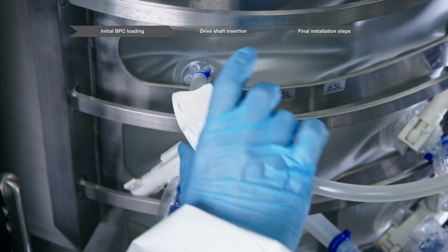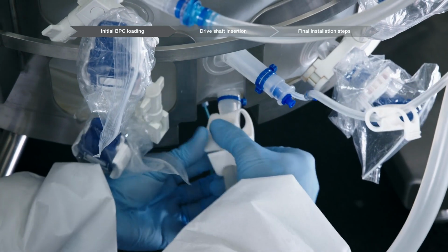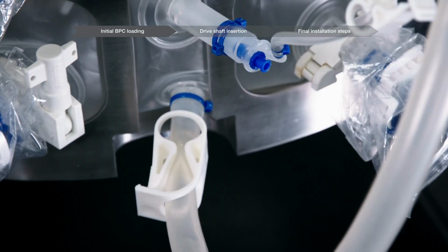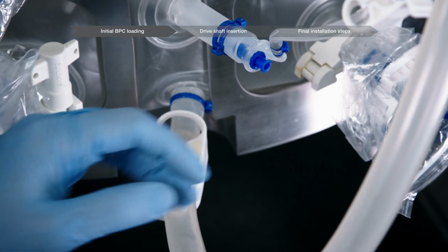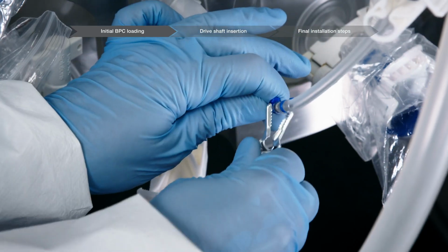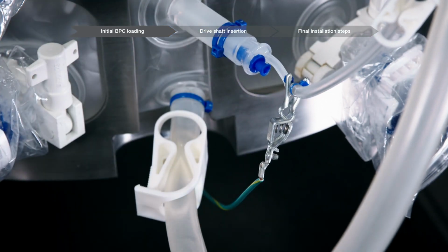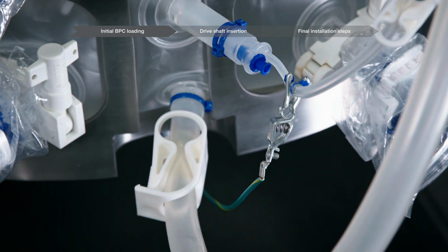Verify all port clamps are closed and located as close as possible to the body of the BPC. Connect the media ground clip to the stainless steel insert in the sample line on the BPC. This step grounds the media inside the BPC and helps to eliminate electrostatic charge.